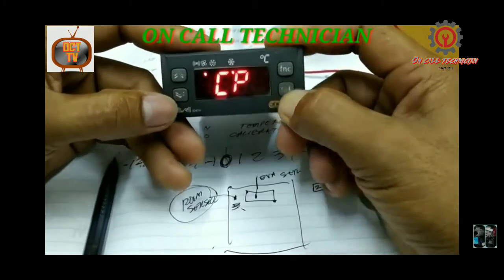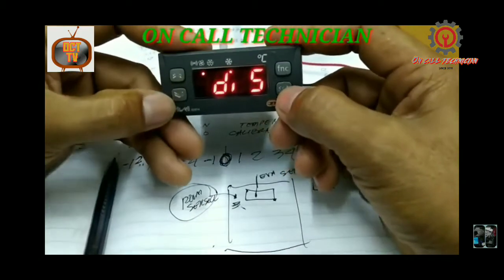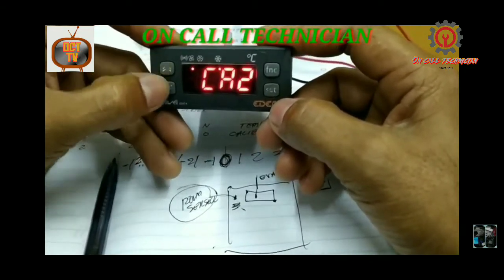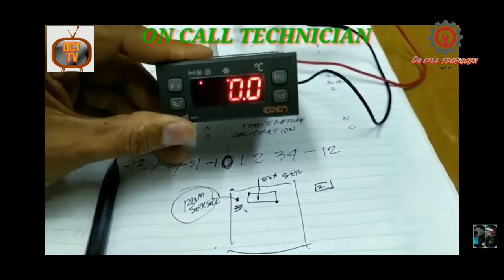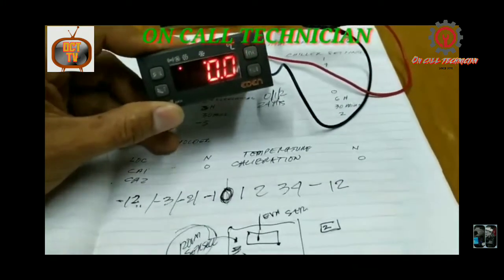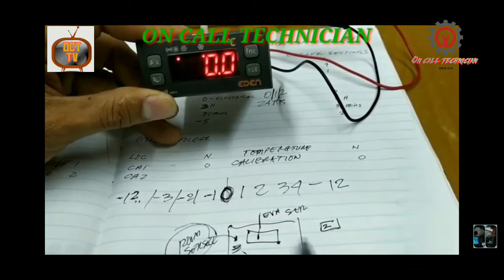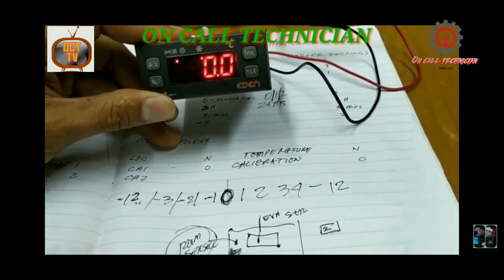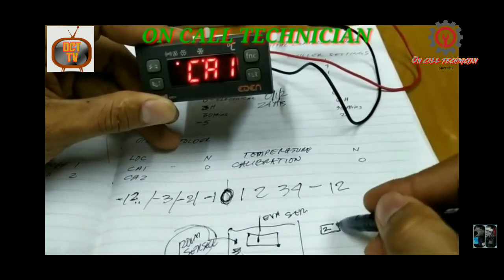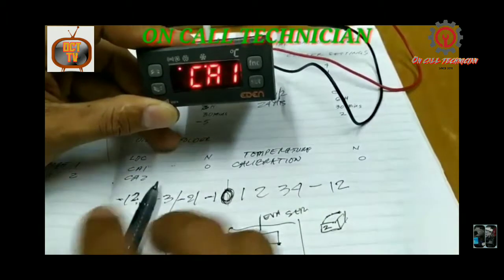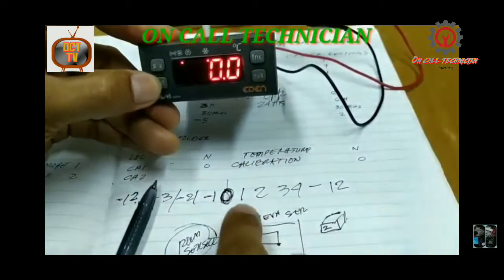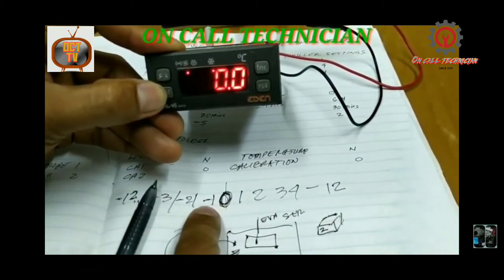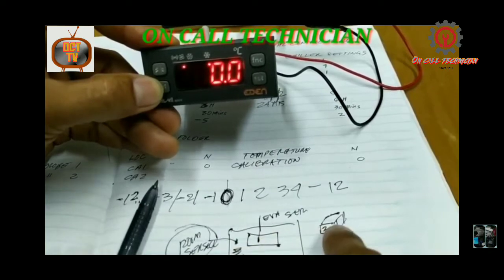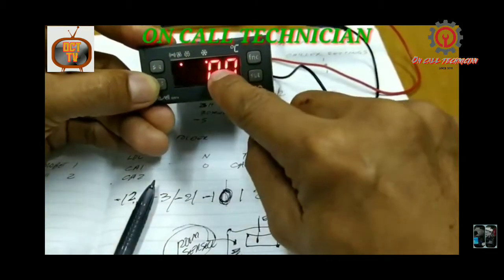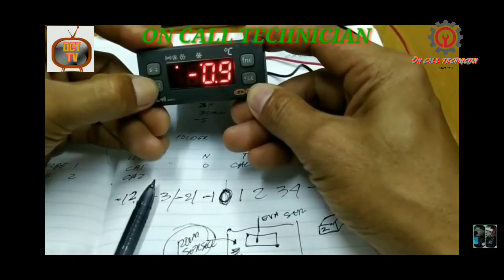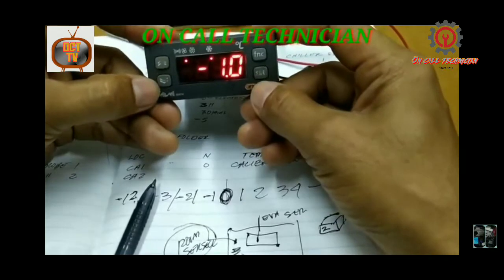So let's enter and go to display, and let's locate the CA1. If you want to calibrate that one, since we have a 3 differential, if you want to equalize the display with the room cabinet, you need to adjust the 0 to negative 3. Let's enter again. You need to go to -3, not +3, guys. If you go to +3, just change it, go to -3. Just press the arrow down button.